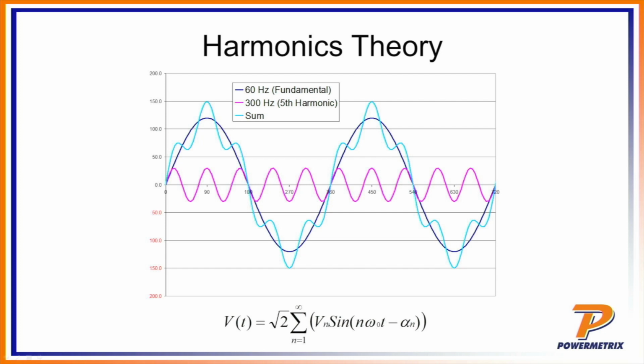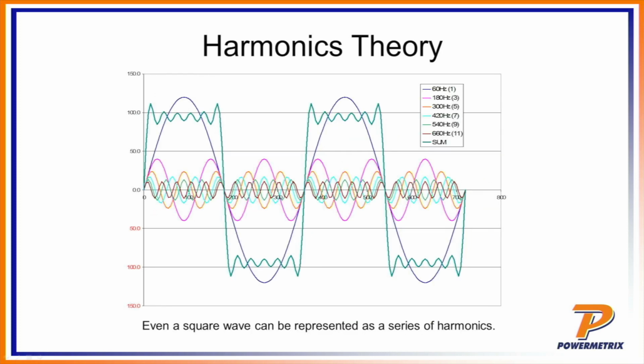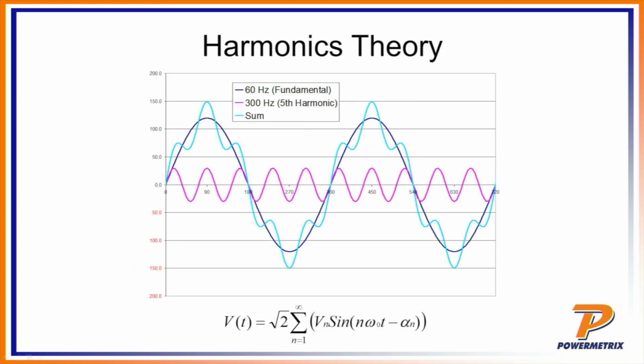If we take a more practical example of that, let's say we've got a 60 hertz waveform, which is the dark blue waveform on your screen. If we take a 300 hertz harmonic, 300 hertz is the fifth harmonic, 5 times 60 is 300, and we sum those together, what you end up with is this light blue waveform. And so this would be something that has a fair amount of harmonic energy on it.